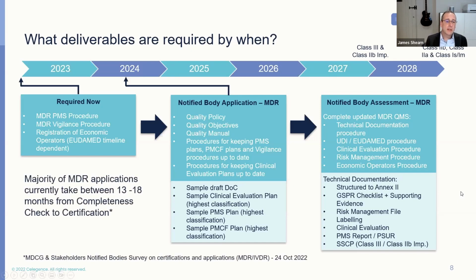It's very important to recognize that when planning the timeline for the MDR transition, even in light of these proposed changes, the assessment time for MDR is quite long. So in accordance with a recently published survey by the Commission on the progress of applications through notified bodies, it typically takes between 13 and 18 months for an application to go from the completeness check through to certification. So while this timeline may appear quite long in the context of doing an application or multiple applications for multiple products, the timeline is still quite long, and that needs to be accommodated.